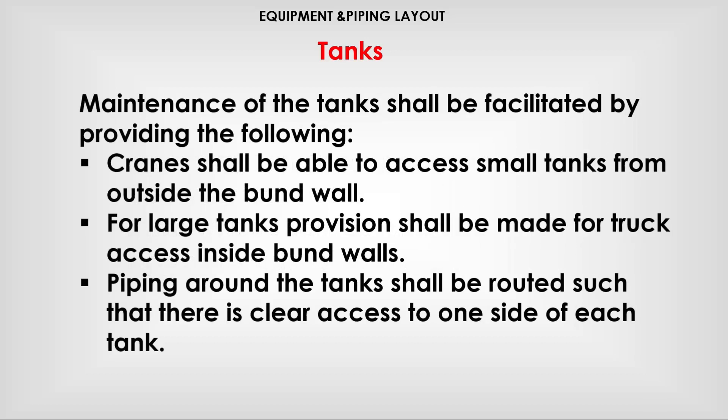Maintenance of the tanks shall be facilitated by providing the following. Cranes shall be able to access small tanks from outside the bund wall. For large tanks, provision shall be made for truck access inside bund walls. Piping around the tanks shall be routed such that there is clear access to one side of each tank.